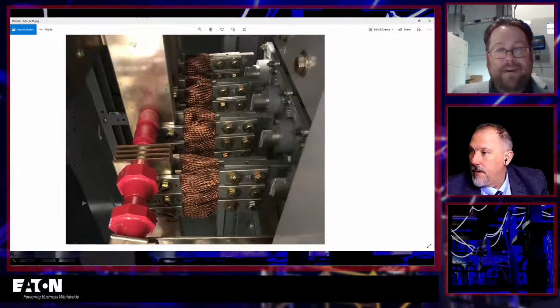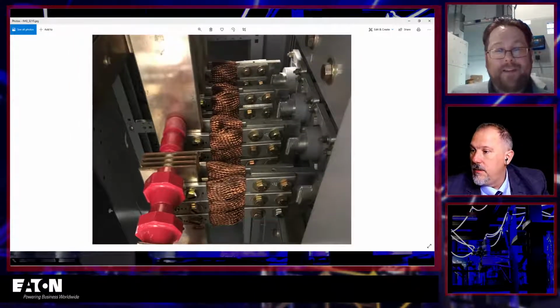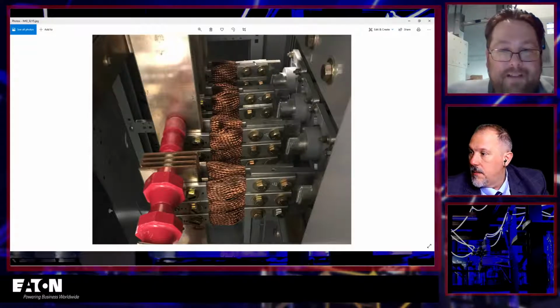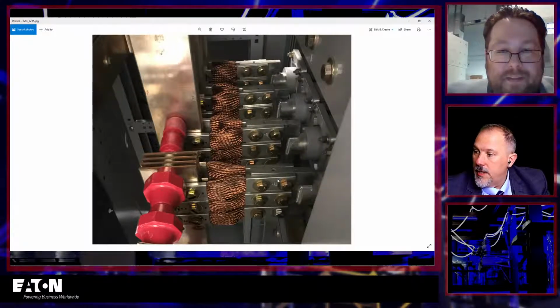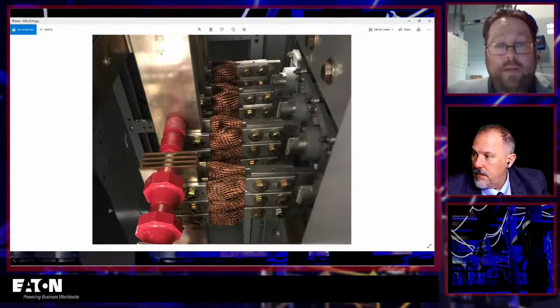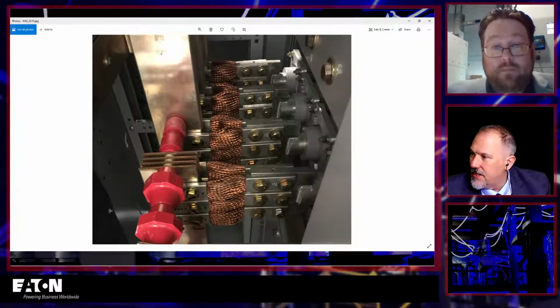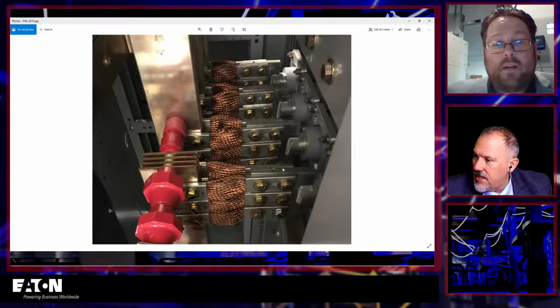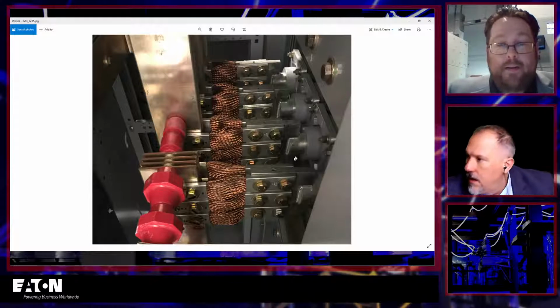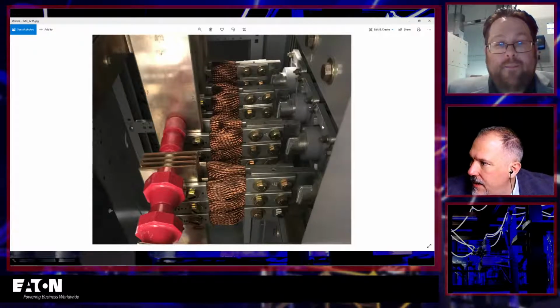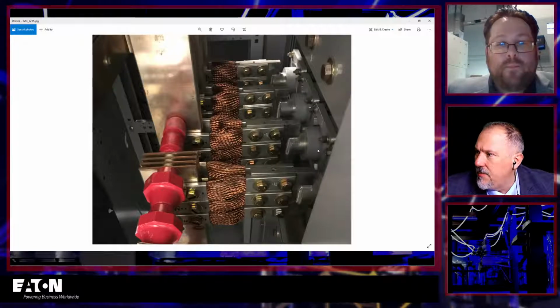And then looking to see, this is a close up. That's a close up of the right hand side coming off the transformer. So you got phase A, B, C, front to back. There's your neutral connection, and the ground is not actually in the picture, I don't think. So the one closest to us here is A. No, that's neutral. I was going to say, because these three look like A, B, and C, and so it's A, B, C, and then neutral. Correct. Now that looks, shouldn't these be labeled A, B, and C somewhere here?